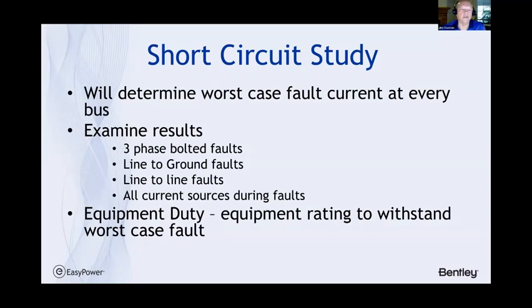Probably the most dangerous facilities are the ones that have high motor contribution, because large motors can end up acting like a generator during a faulting event. And then in addition to the maximum current produced, we need to create or evaluate the equipment duty, which Justin referred to as one of the requirements of a normal working system, and that is the equipment's rated to withstand the worst case fault. And that's dependent upon the maintenance and the condition of the equipment to ensure that it's going to work if it's needed.